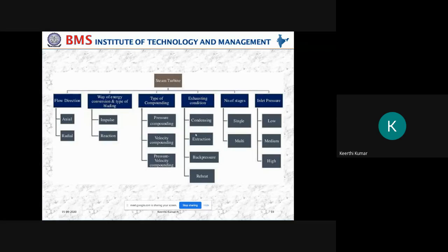Based on exhausting condition, that is condensation, extraction, back pressure, reheat. Based on the number of stages, single stage and multi-stage. Based on inlet pressure, low, medium, and high pressure. If it is low, we'll go for single stage. If it is medium, also single stage. If the inlet pressure of the steam is very, very high, we'll not restrict ourselves to a single stage. We'll go for multi-stage turbines. So based on this only, single stage or multi-stage depends.